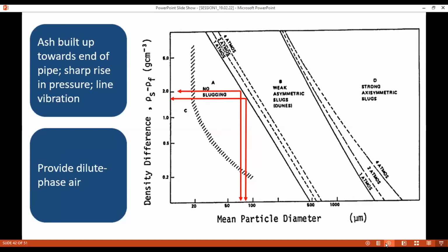And you know how you know that is happening? You typically have blockage towards the end of the pipeline. So typically near the vertical, you have blockage there. You sometimes have pipe vibration, and you have a rattling sound. It is like cut, cut, cut, cut, cut. You sometimes get this kind of sound when you have group B material.